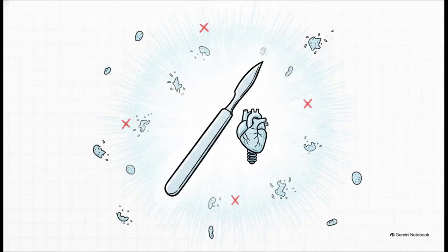At the very top of that list, we have critical items. These are tools that enter the bloodstream or normally sterile tissue. Think cardiac catheters, implants, surgical instruments. Because the infection risk here is frankly catastrophic, we absolutely have to achieve a sterility assurance level of 10 to the negative 6. To put that into perspective, that means there can only be a 1 in a million chance of a single surviving bacterial spore. It's an incredibly rigorous standard, as it should be.